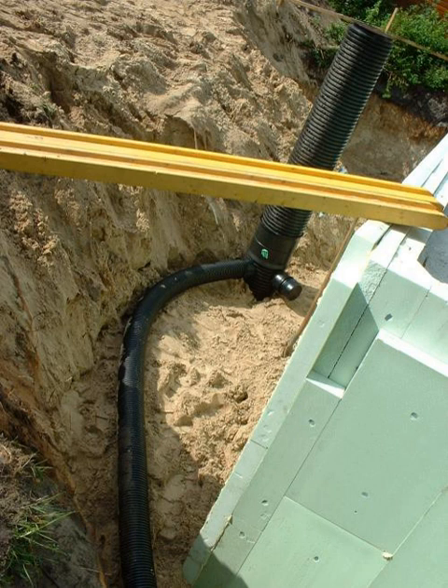Joints connecting the tubes must be tight enough to prevent water or gas infiltration. In certain geographic areas, it is important that the joints prevent radon gas infiltration. Porous materials like uncoated concrete tubes cannot be used. Ideally, earth tubes with antimicrobial inner layers should be used to inhibit the potential growth of molds and bacteria within the tubes.